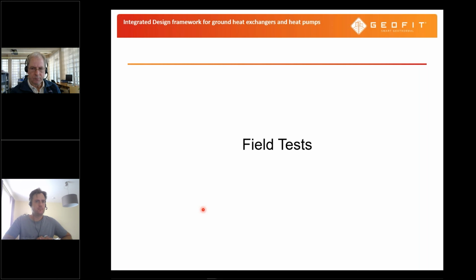Yeah, I can also tell a little bit about it. We were involved in a European research project developing a propane heat pump with a ground source system. It was actually a heat pump that was used indoors. It was the GeoCool project. It was around a 17 kilowatt unit. Propane was used as a drop-in refrigerant for a heat pump that normally ran R134A. And we achieved over 30% higher efficiency compared with 134A, and also with less than 500 grams of refrigerant, we had a capacity of around 16-17 kilowatts.